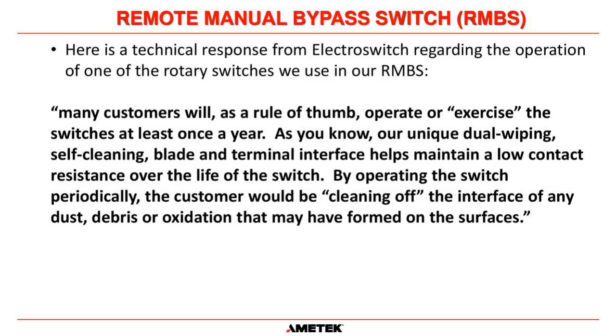moved. So here's a technical response from ElectroSwitch. They are the manufacturer of the majority of our rotary bypass switches. And they said that many customers will, as a rule of thumb, operate or exercise the switch at least once a year. And he goes on to say, as you know, there is a unique dual wiping, self-cleaning blade and terminal interface, which helps maintain a low contact resistance over the life of the switch. So therefore, by operating the switch periodically, the customer is cleaning those interfaces of any dust, debris, or oxidization that may have formed on the surfaces.